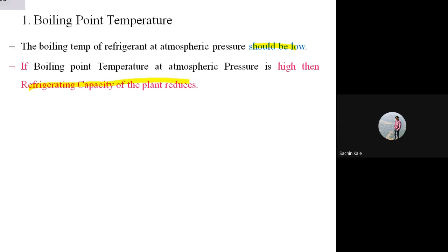Why? Because the boiling point temperature of R11 is 23.77 degrees centigrade. That means about 23 to 24 degrees centigrade positive. So it will not be possible to obtain ice with that R11 refrigerant. You have to choose a refrigerant with the boiling point temperature as low as possible. If the boiling point temperature is higher, then the refrigerating capacity of that plant will keep reducing.